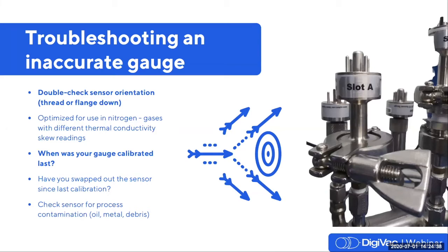Most importantly, remember that the gauge will not read accurately if the sensor is not mounted upright. Double check your sensor orientation and ensure that the thread or flange are facing down.